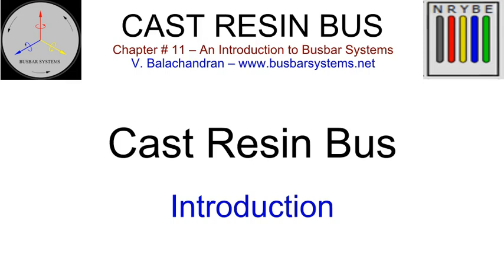Cast Resin Bus. Introduction. With the development of epoxy resins as an insulation material for the switchgear component and the establishment of busways as a viable alternative to bus ducts in certain areas of application, it was but natural to explore the possibility of developing a cast resin bus for low and medium voltage applications. While the application of busways is limited to its usage in low voltage distribution, Cast Resin Bus offered an opportunity to extend its application to medium voltage distribution.